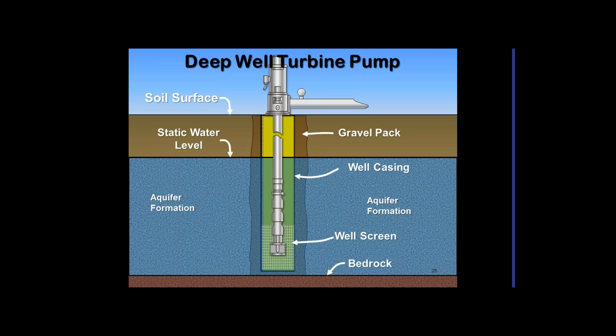With a deep well turbine pump, when it's on, water is going to be coming up and out. One of the things we want to ensure is, one, that the well can supply enough water coming in, and that we have enough height between. When the water is pumping, this static water level is going to be somewhat less. So we want to make sure that this height is greater than the net positive suction requirement so that we prevent cavitation. That's an important factor, and we can test for that in doing a well test.